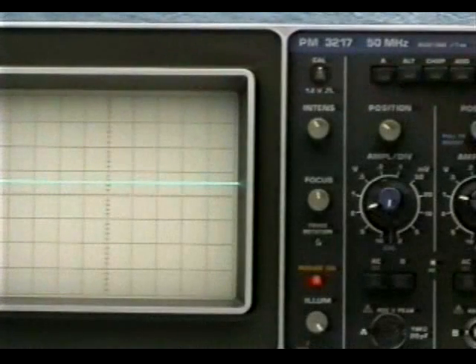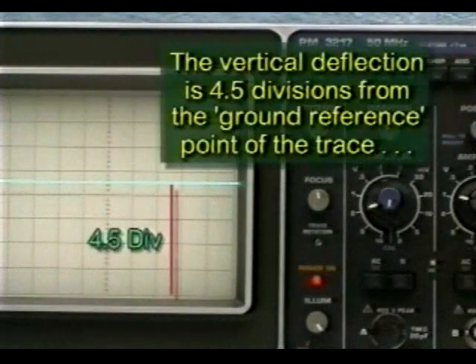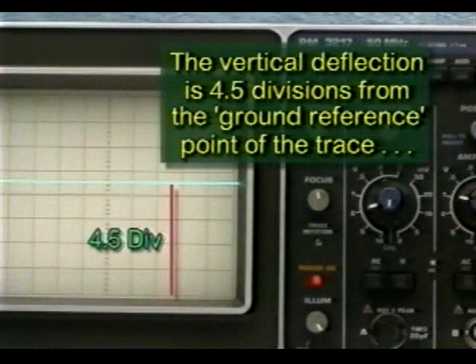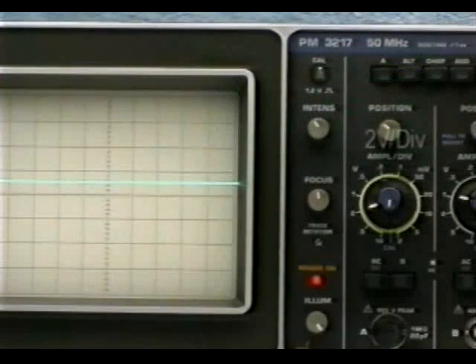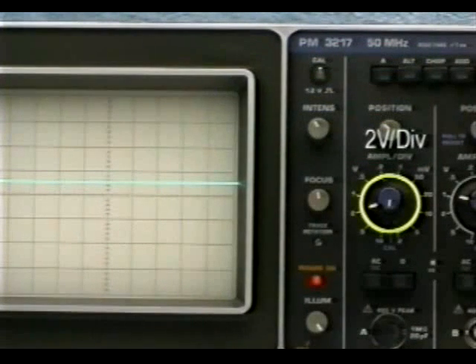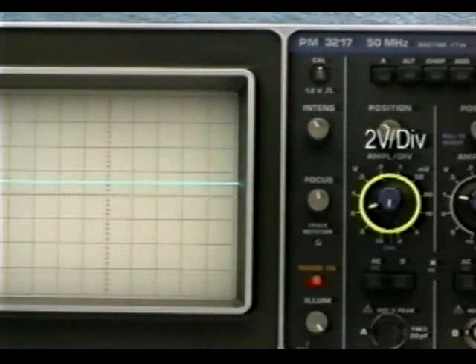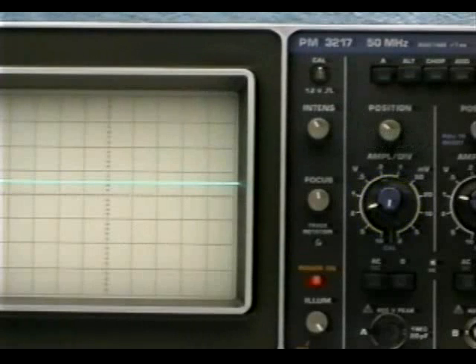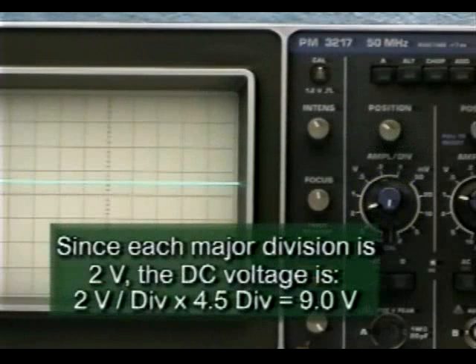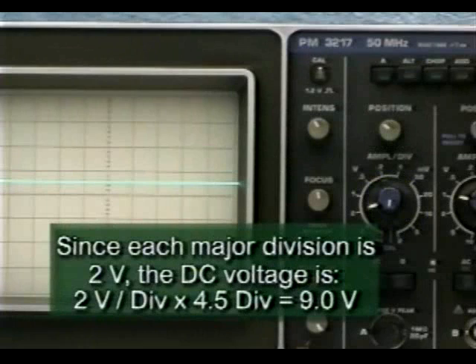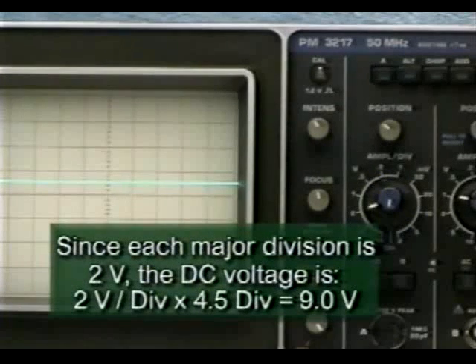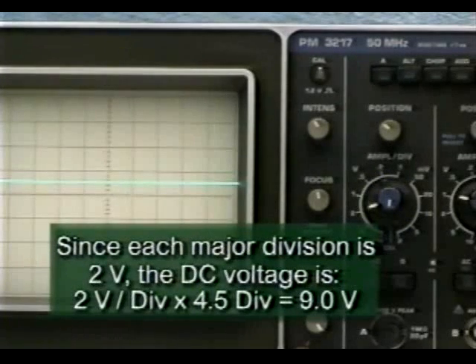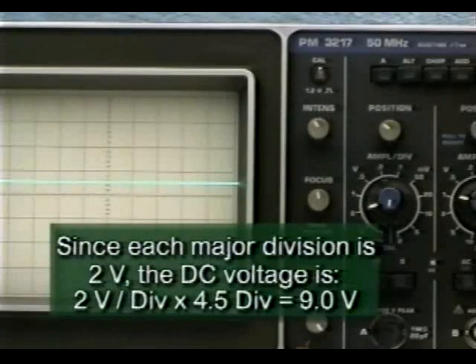In this example, the beam is deflected 4.5 divisions vertically from the ground reference point. The vertical attenuator setting is set to 2 volts per division. Since each major division is worth 2 volts, the DC voltage is 2 volts per division multiplied by 4.5 divisions or 9 volts.